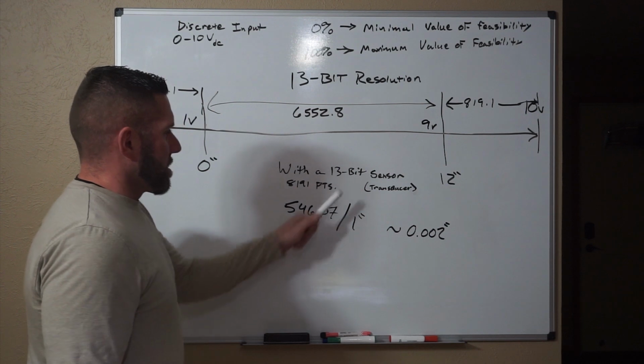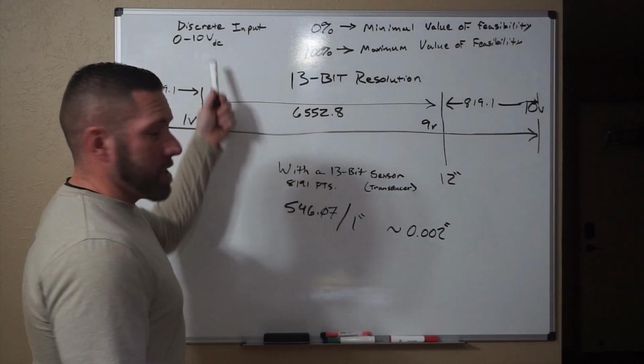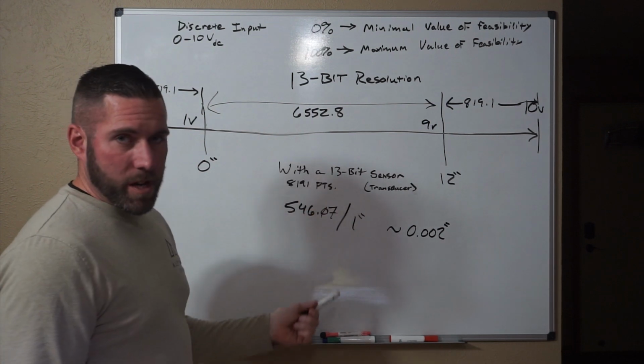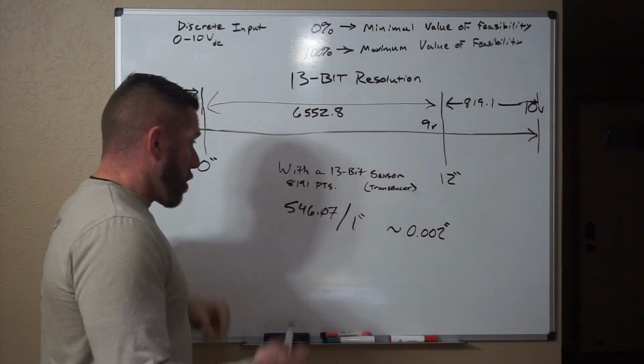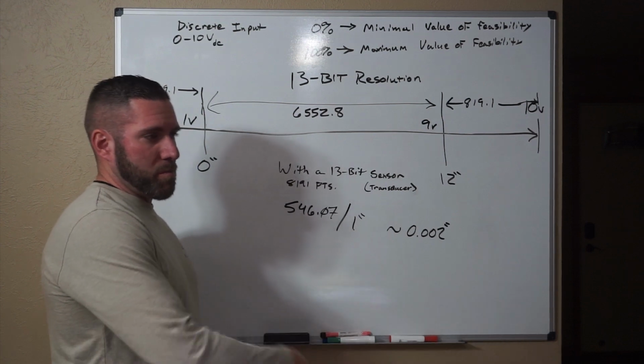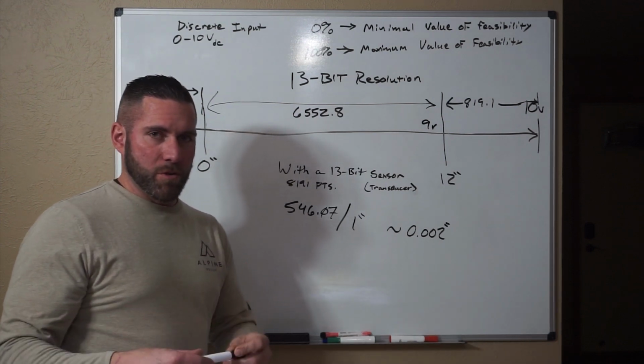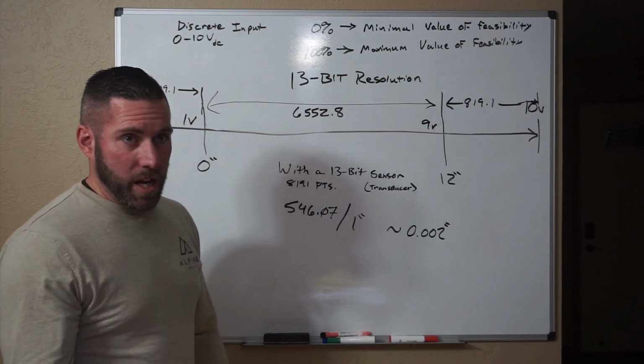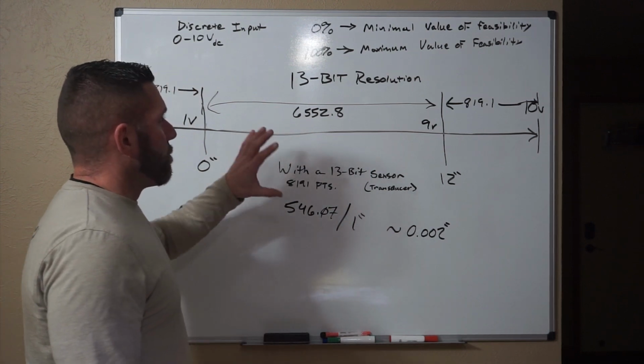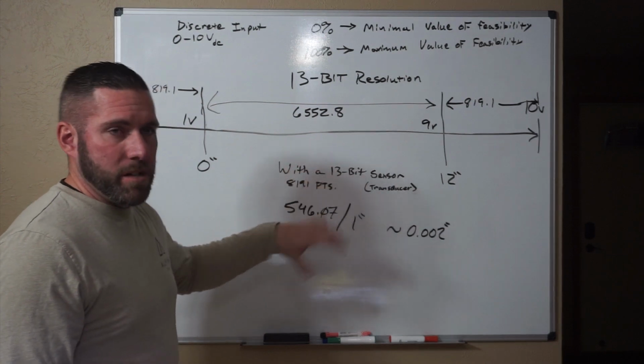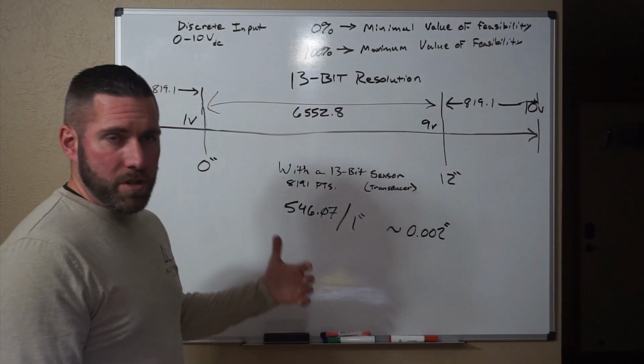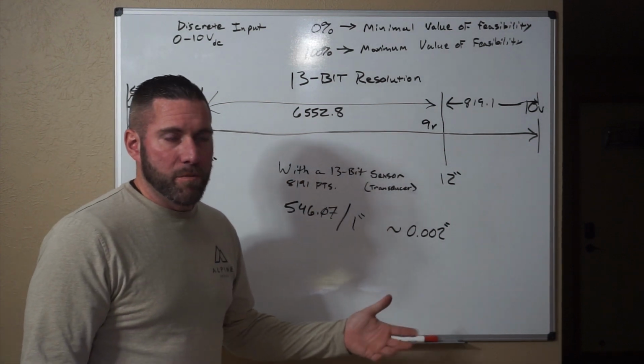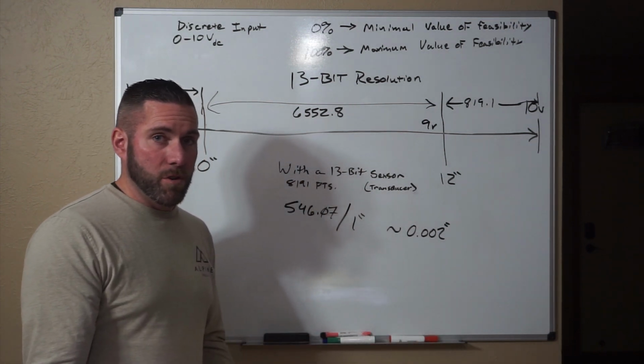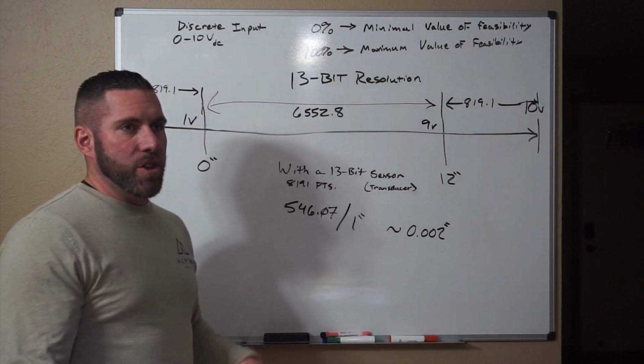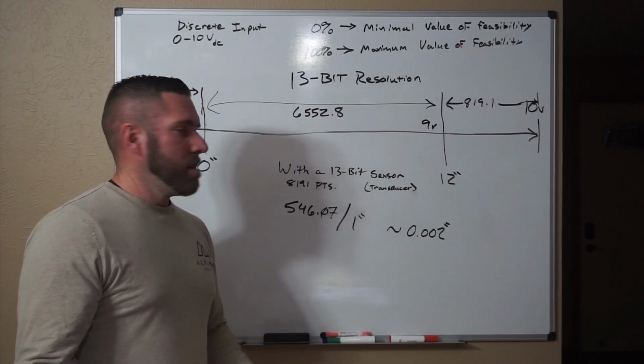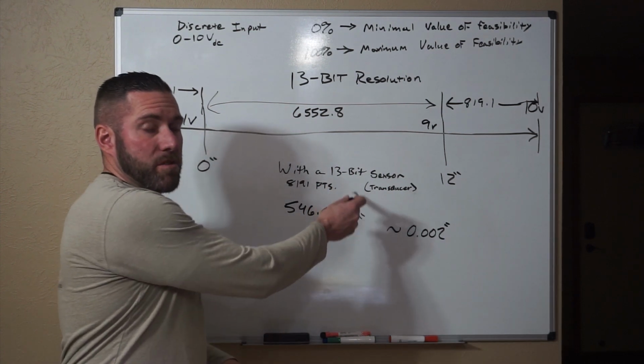So, like I said, with the resolution thing, depending on what the PLC can read is what's going to dictate whether or not you get that kind of a sensor. So while the sensor is putting this out and you're getting alarms and problems are happening, you need to remember that resolution also applies to frequency and the range of view. So when you're reading this stuff on like an HMI, or you're looking at graphs on Pi tools, or you're looking at something on a multimeter, maybe a Fluke 190 for a portable oscilloscope, 2 and 4 channel, things like that, you should be cognizant of the idea that this might be talking faster than the tool you're using.